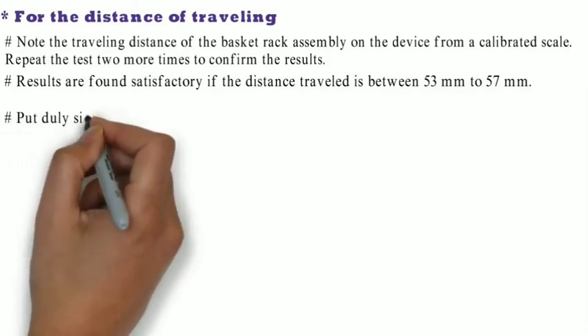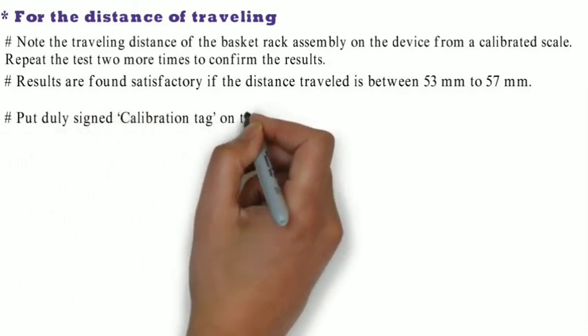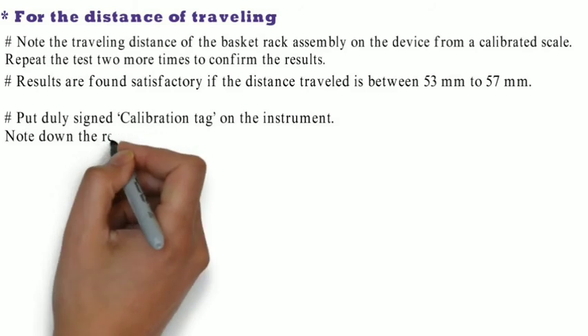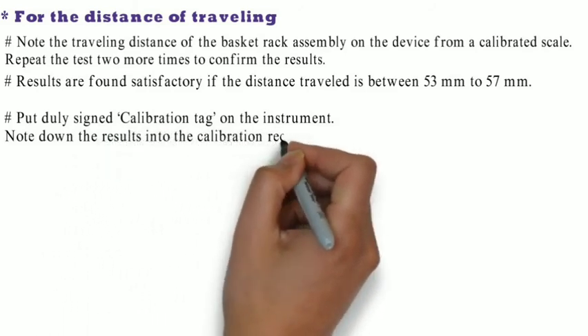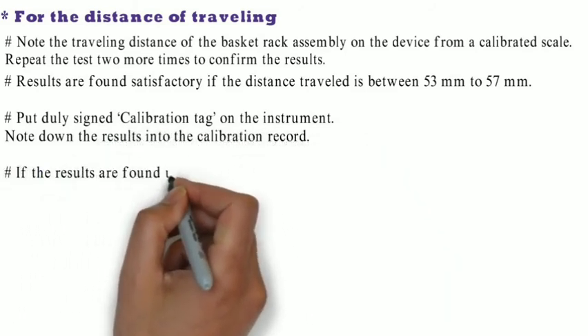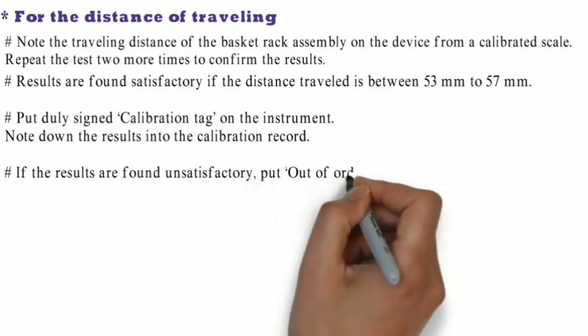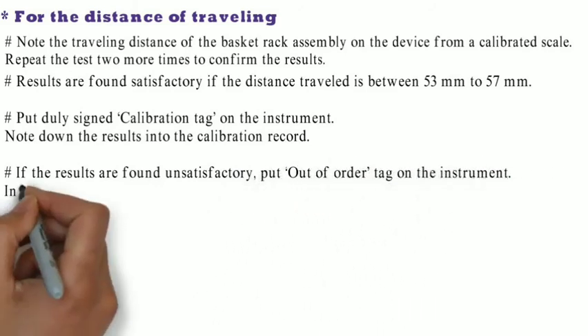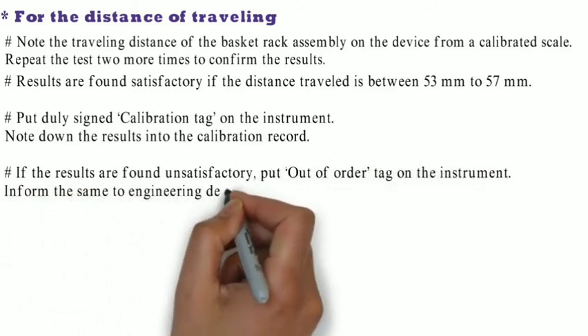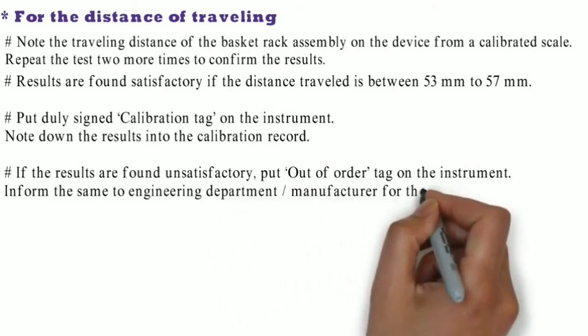Put a duly signed calibration tag on the instruments. Note down the results in the calibration records. If the results are found unsatisfactory, put an out of order tag on the instruments, and inform the engineer and the manufacturing department for their repair. SOP for calibration of disintegration test apparatus.